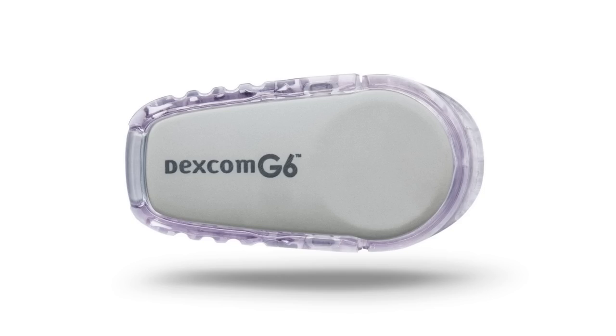It's funny you say that, because as part of the classification, what the FDA did with us with the special controls around this de novo approval, one special control is that the sensor has to shut off at the end of the period it's been proven clinically accurate, so patients can't restart it anymore. And with a no-calibration algorithm, you can understand the science behind that, because a brand new sensor behaves differently than one that's been in your body for 10 days that you'd restart.